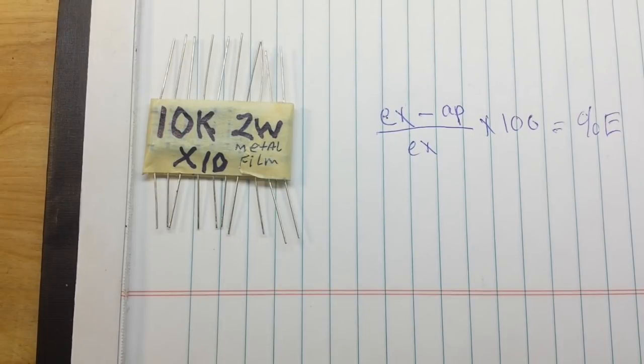We're going to use the Fluke 8840A multimeter to do a four-wire measurement for that, a Kelvin measurement. That's going to give us our most accurate measurement, and we're also going to back up our readings by checking them against some other multimeters. So let's get started doing that.